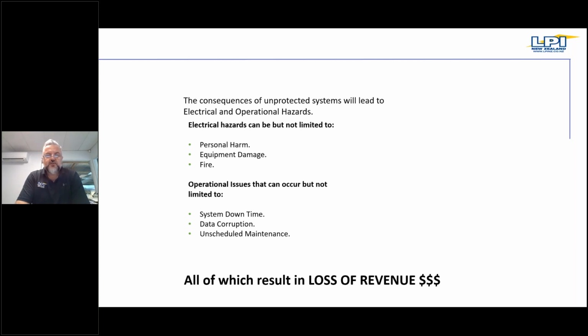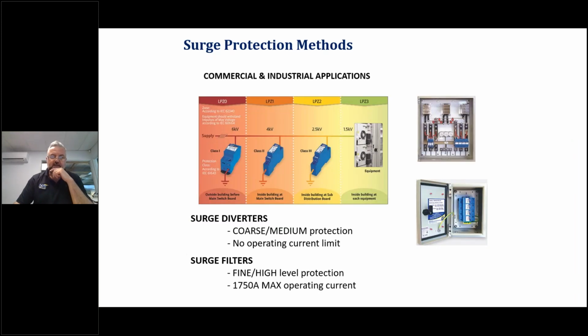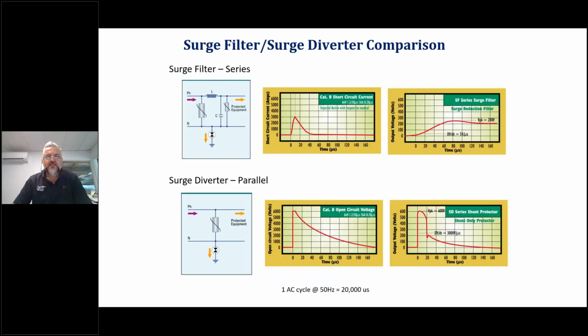Also, any damage due to surges will cause unscheduled maintenance, which again will cost money. There are a number of different types of surge protection, depending on what class is required and what level of protection you require. And again, we can address that in different areas. It's important to mention that there are two types of surge protection. One is surge filters, and the other one is surge diverters.